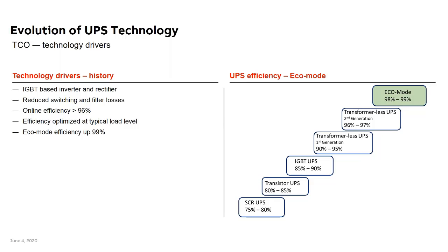because we are seeing a new generation of semiconductors, silicon carbide, becoming available. One UPS manufacturer has started using them, but only in one UPS, and they did not use it in the latest generation. Silicon carbide has even fewer losses compared to IGBTs, and with that we can get an efficiency very close to 98% in double conversion online mode, which of course will lower the incentive for economy mode even more.